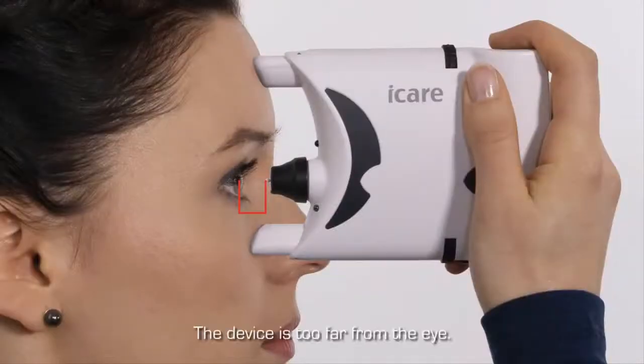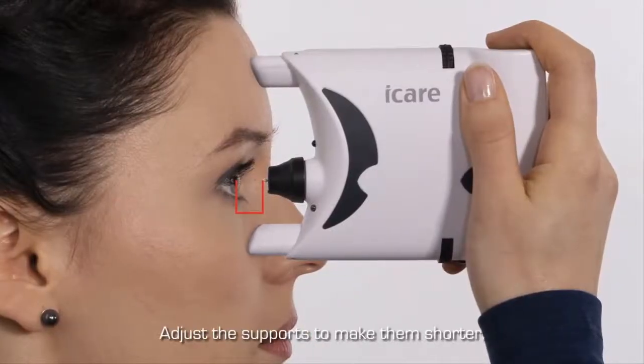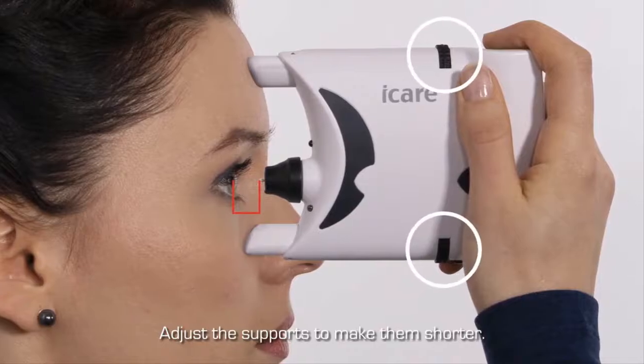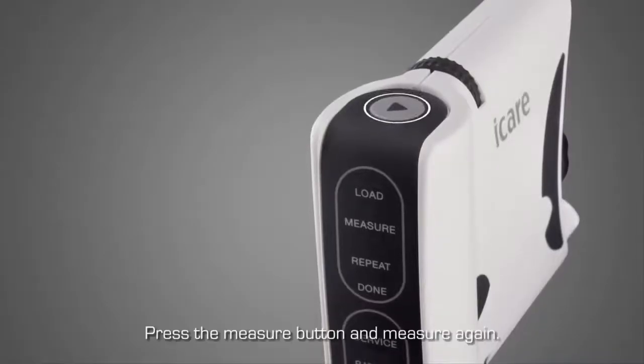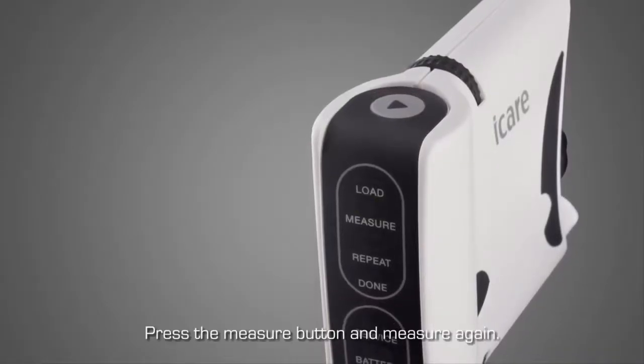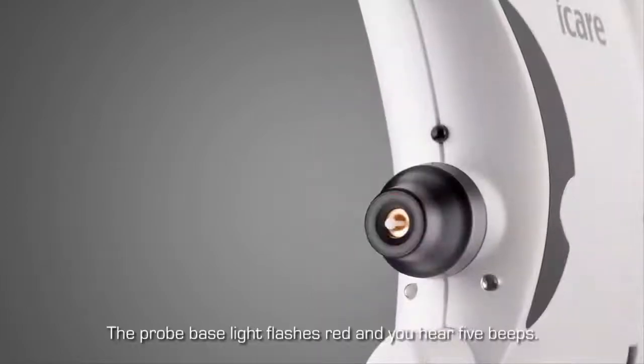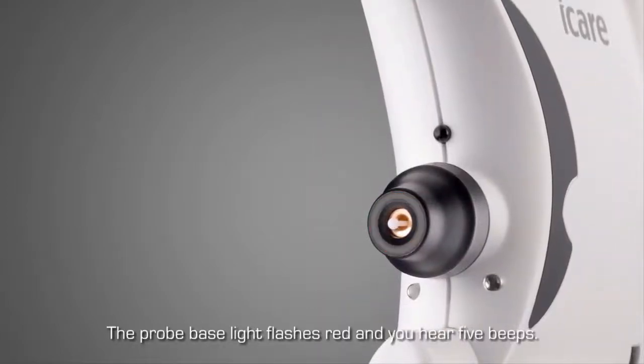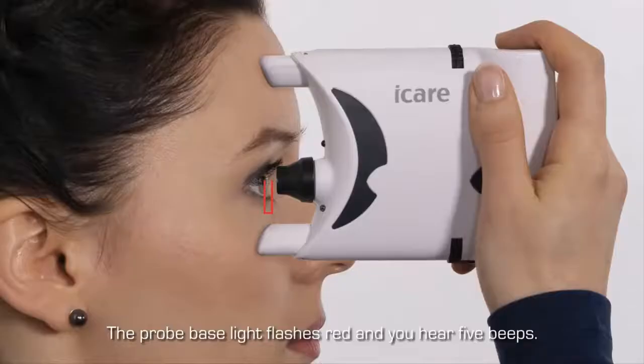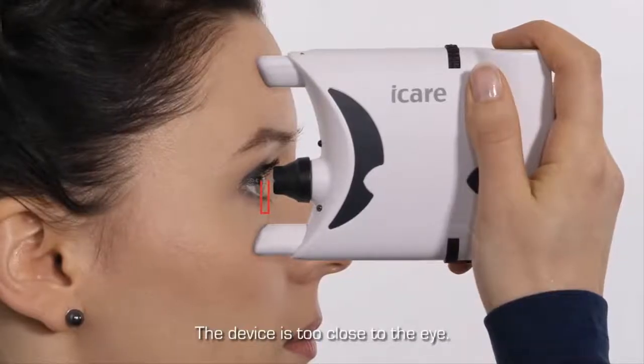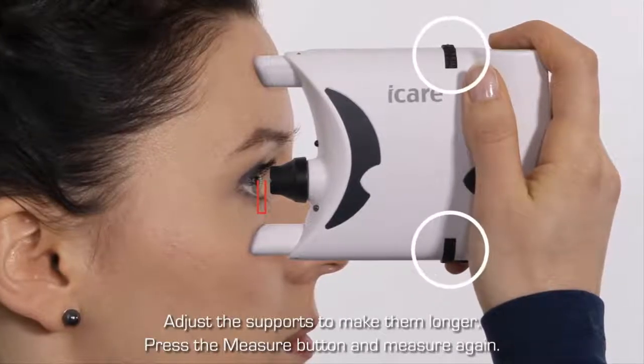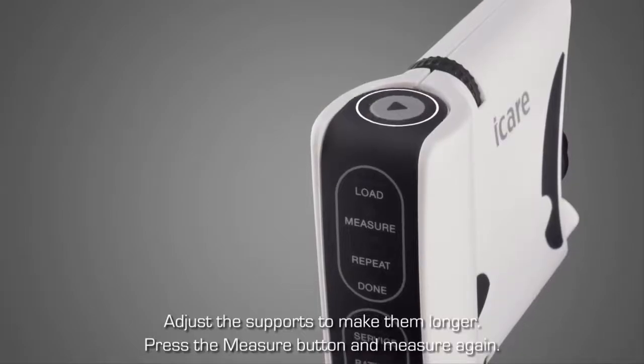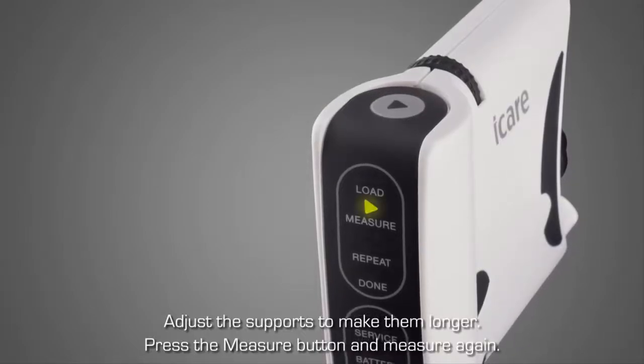The probe base light flashes red and you hear 3 long beeps. The device is too far from the eye. Adjust the forehead and cheek supports to make them shorter. Press the measure button and measure again. The probe base light flashes red and you hear 5 short beeps. The device is too close to the eye. Adjust the forehead and cheek supports to make them longer. Press the measure button and measure again.